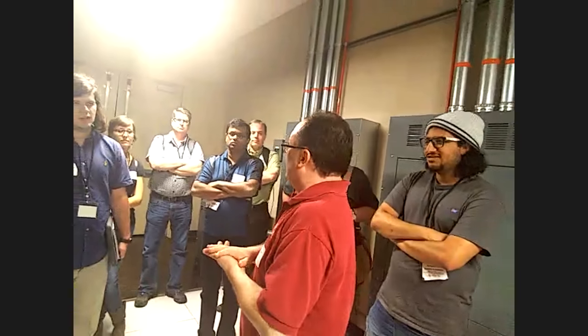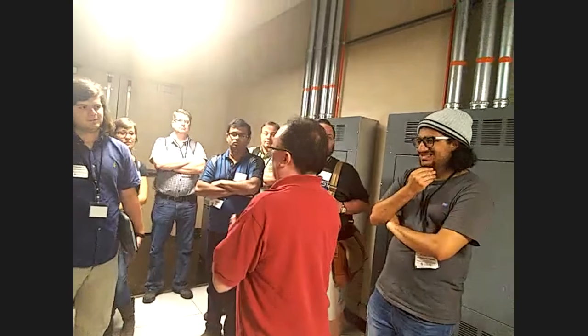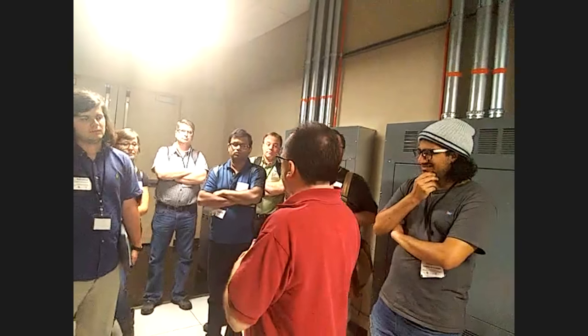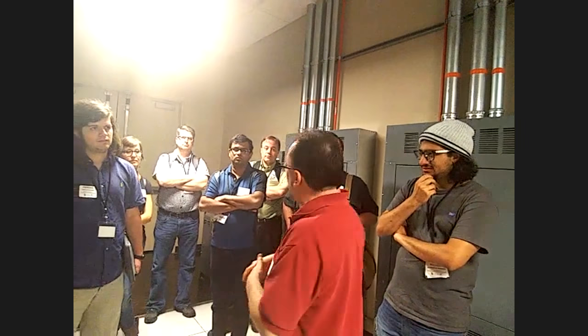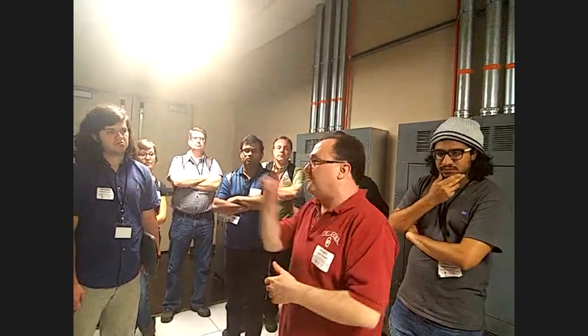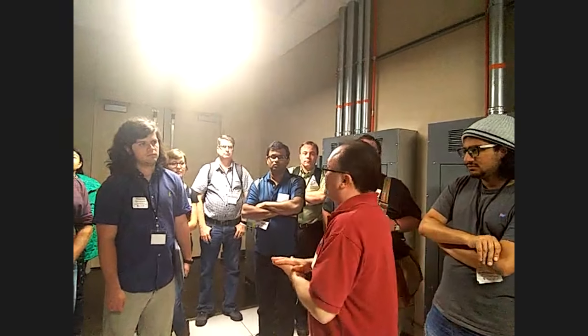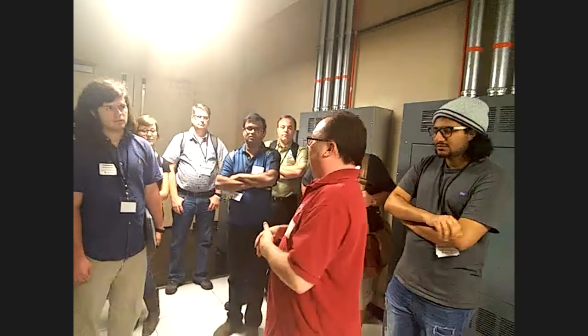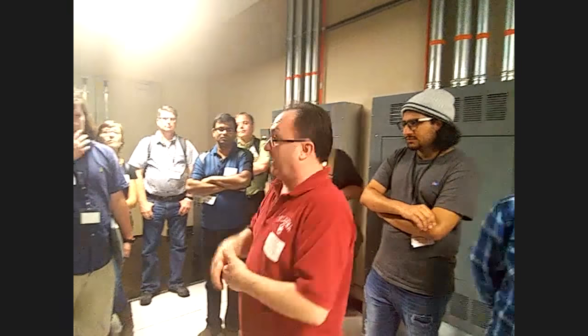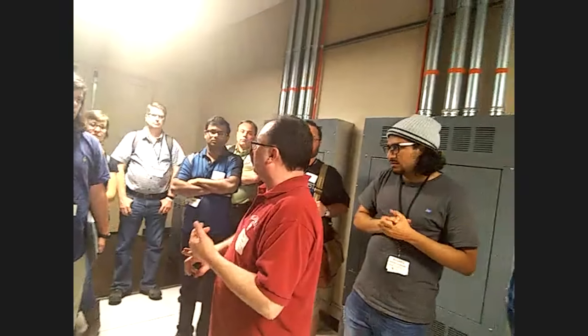Never stops. What happens if it stops? Exhausted, so the heat rises. Temperature rises at 1 degree Fahrenheit every 45 seconds until one of two things happens: either we shut down or we melt down. Which one do we choose? Shut down. So we will auto shut down if the temperature gets above the threshold. And well before it gets to that threshold, we get a panic that we need to scramble, we get text messages and emails saying scramble the jets now.